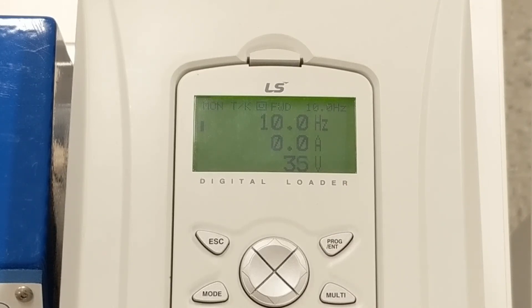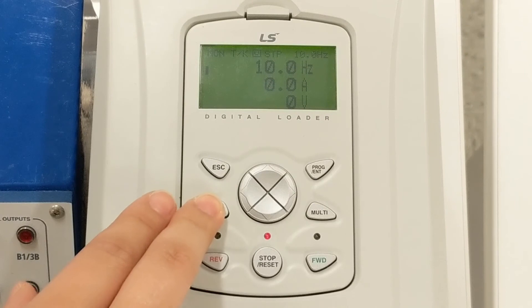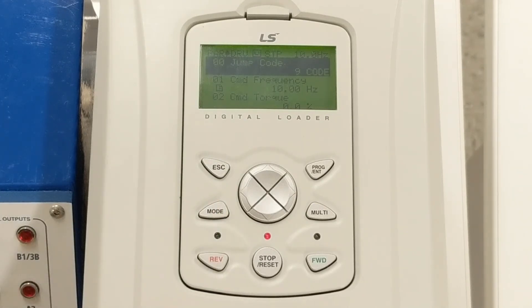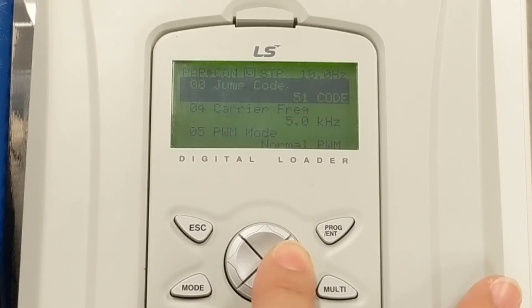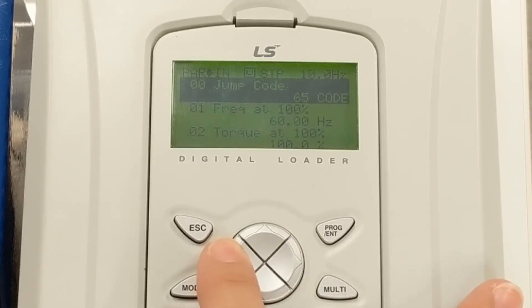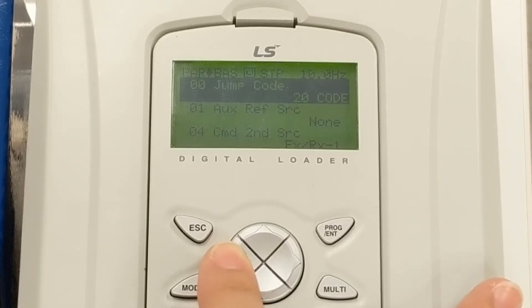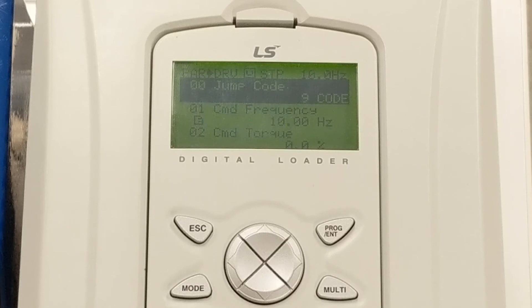Let's say we have an application which is using an external 0 to 10 volt speed pot. To set this up, we must go into the parameter mode. Pressing the mode key will change the keypad mode to the parameter display — we can see this because PAR is displayed in the top left corner. To the right of PAR is the parameter group; here we see DRV. Pressing the right arrow, you will see numerous groups: BAS, ADV, and more. These parameter groups are broken down into an easy to remember order, and the list can scroll both ways by pressing the left or right arrows. The most common parameters are set in the DRV and BAS groups. For a full list of parameter groups and settings, refer to the S100 or IS7 user manual.